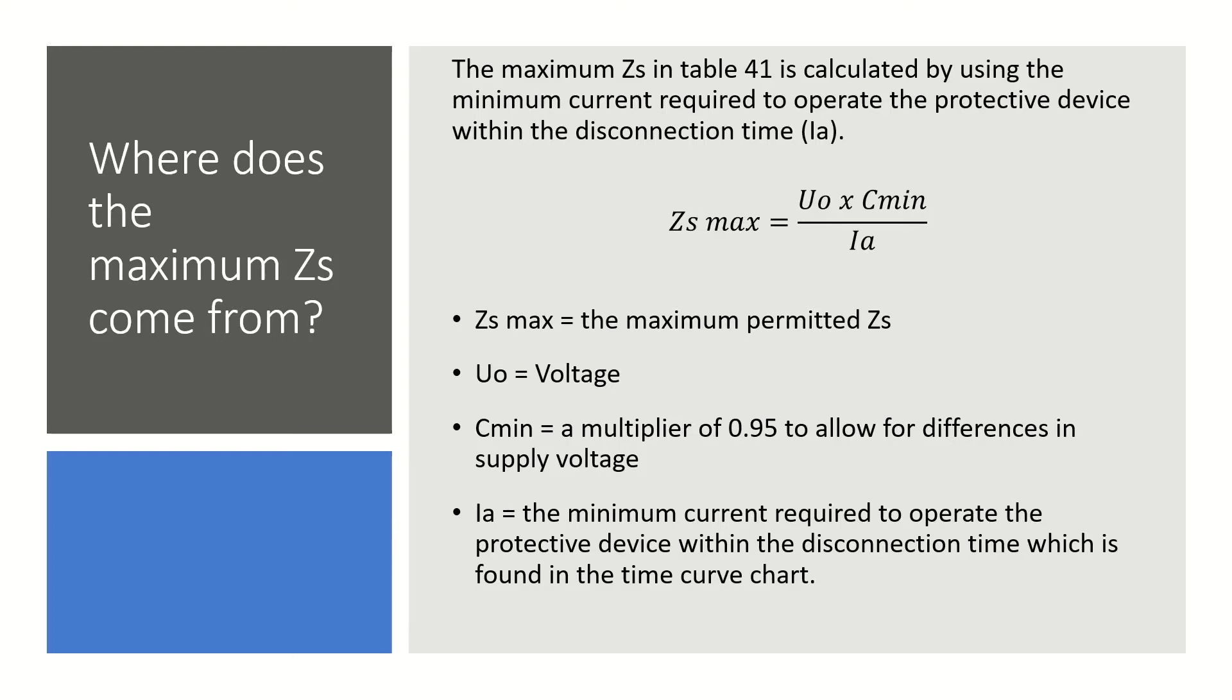The values for Ia can be found on the time curve chart for the protective device. For protective devices that are included in the time curve charts in BS7671, there is a table next to the chart which shows the minimum current to operate the protective device within the disconnection time. For devices that aren't shown in BS7671, such as MCCBs, the information can be requested from the manufacturer.